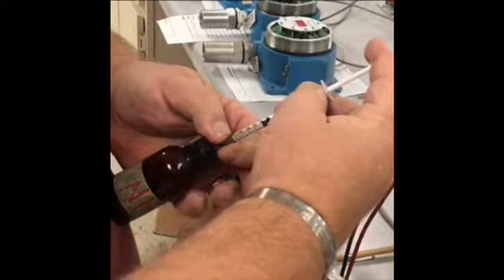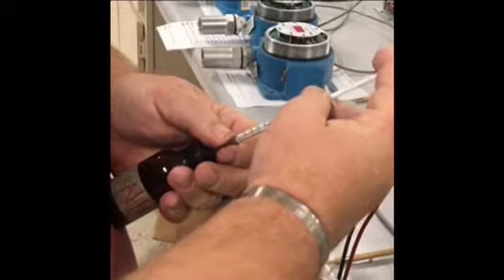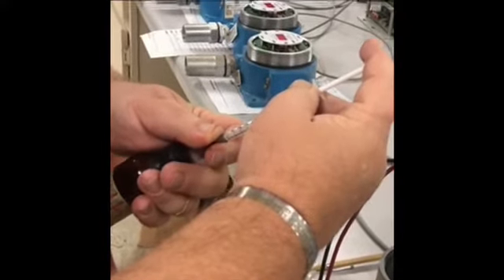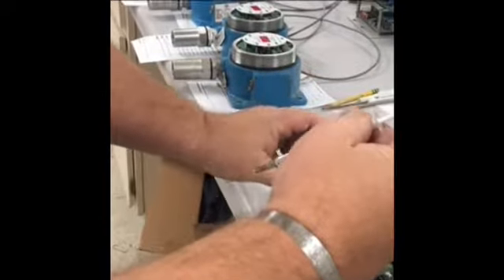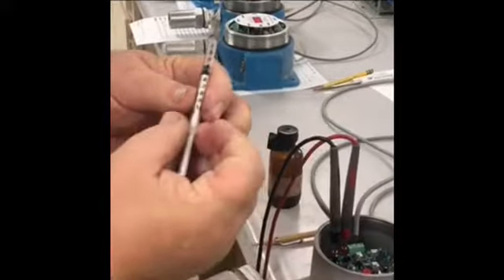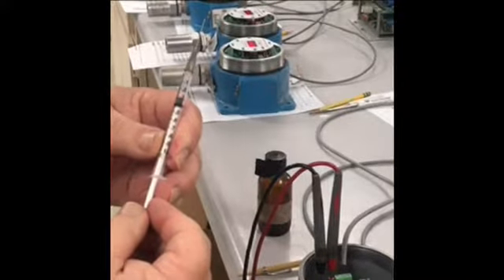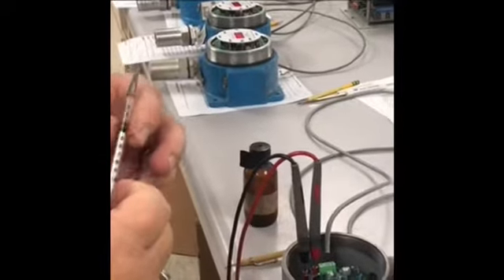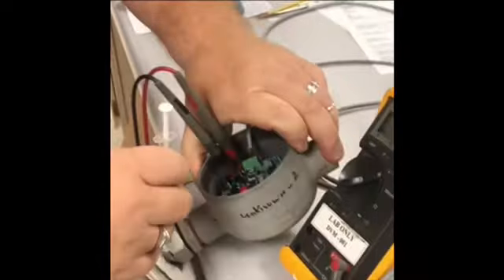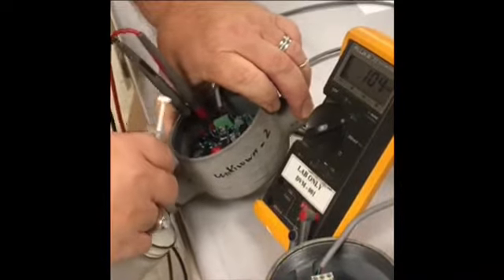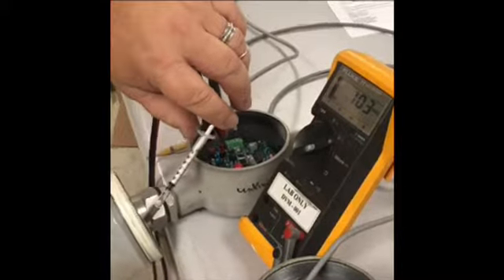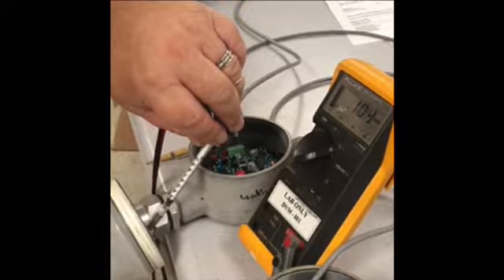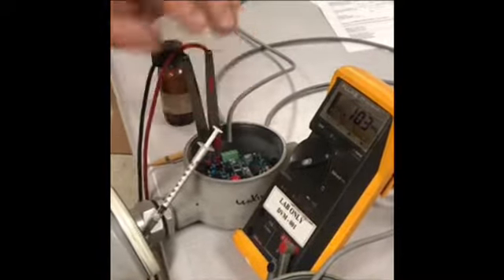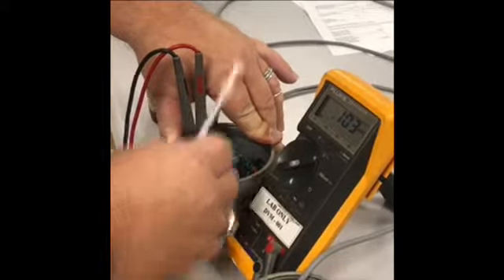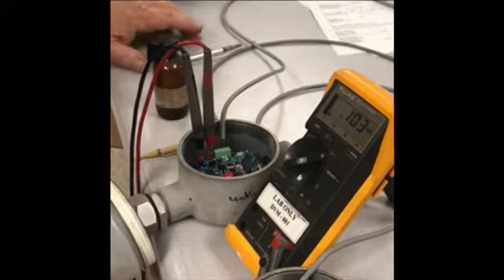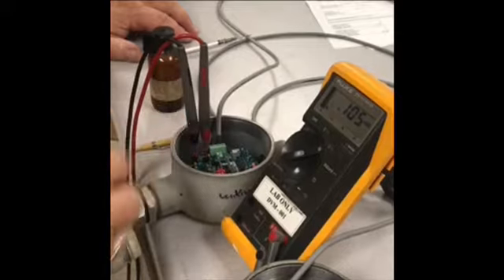Make sure you put your fingers on the needle and help the needle come out of the bottle instead of just pulling on the syringe so it doesn't get separated, because if that happens again, you'll lose the gas from the bottle. So pull the needle out, and we're going to go ahead and just push the plunger down to exactly 0.3, letting the excess gas escape out of the needle. Then we're going to take the needle, push it through the rubber septum of the calibration canister, and carefully push from 0.3 to 0.1, injecting that gas into the canister. Go ahead and pull the needle out, dump the remaining gas into the air, and watch the output when it starts to read.